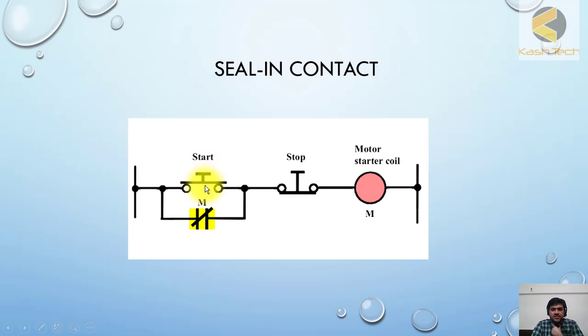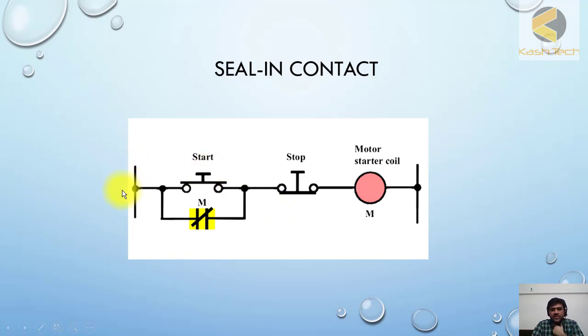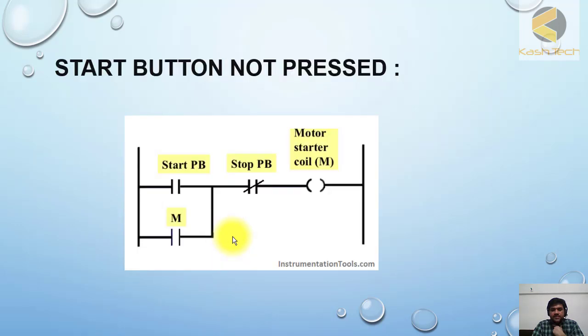Let's see the example: now I have pressed the start button, M is energized. If M is energized, this contact becomes closed. Once this contact is closed, even if I release the start button, the DC circuit path is maintained through this contact and it keeps energizing. So this contact is called the seal-in contact, this circuit is called a latching circuit, and the relay we are using for the latch can be called a latch relay. The contact we are using is called the seal-in contact.